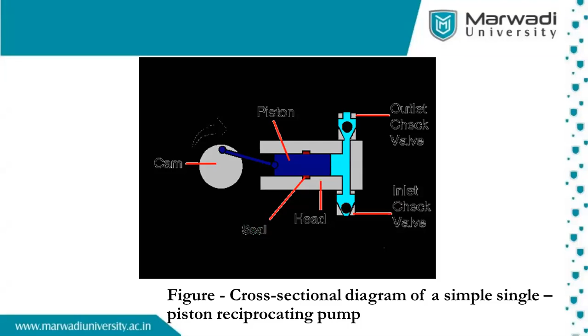Then, as I have already explained for solvent delivery, isocratic means only one concentration you have to give, and gradient means there are two types, low pressure gradient and high pressure gradient. So it depends upon you. First it is a trial and error basis. First you have to see whether the peaks are coming separately or not. When you want more separation, then you have to use trial and error with the gradient system. How to mix, how much of the different solvents you have to take and pass through the column, and slowly you have to see the peak isolation, and wherever you are satisfied, that solvent you have to fix for that particular component mixture.